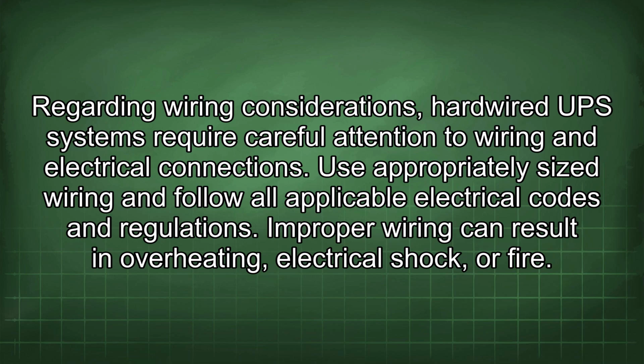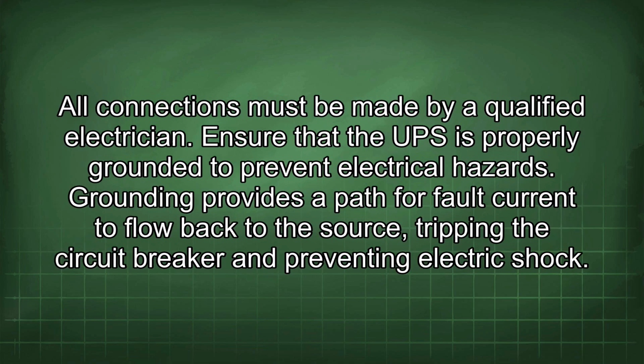Regarding wiring considerations, hardwired UPS systems require careful attention to wiring and electrical connections. Use appropriately sized wiring and follow all applicable electrical codes and regulations. Improper wiring can result in overheating, electrical shock, or fire. All connections must be made by a qualified electrician. Ensure that the UPS is properly grounded to prevent electrical hazards.